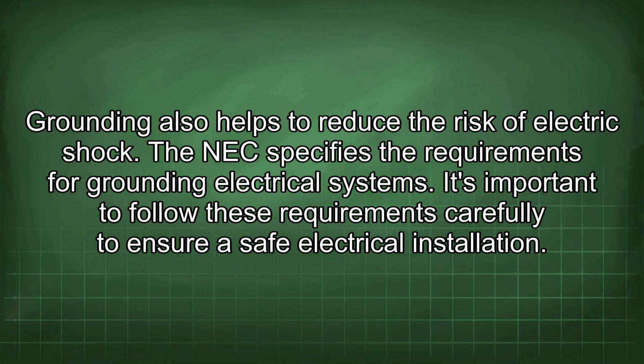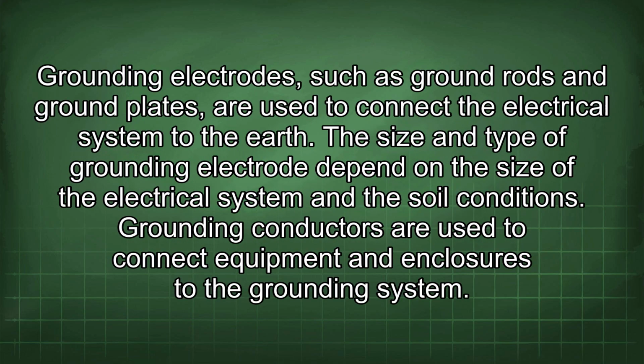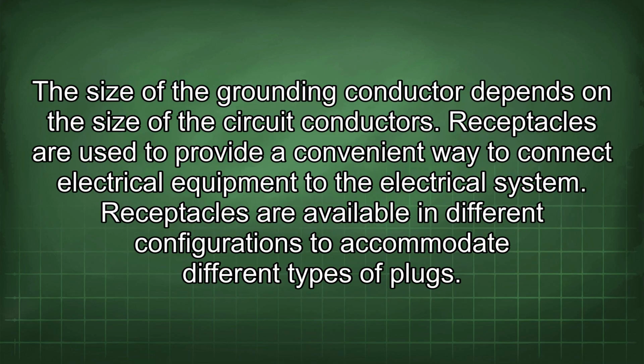The NEC specifies the requirements for grounding electrical systems. It's important to follow these requirements carefully to ensure a safe electrical installation. Grounding electrodes, such as ground rods and ground plates, are used to connect the electrical system to the earth. The size and type of grounding electrode depend on the size of the electrical system and the soil conditions. Grounding conductors are used to connect equipment and enclosures to the grounding system. The size of the grounding conductor depends on the size of the circuit conductors.